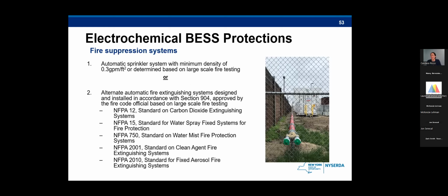So here we have the fire suppression system requirement. This is necessary as a containment response to any thermal runaway or any issues in the system. So these systems can be set up as a sprinkler water system or a clean agent based system. So there is the automatic sprinkler system that requires a minimum water density or whatever is determined based on large scale fire testing.